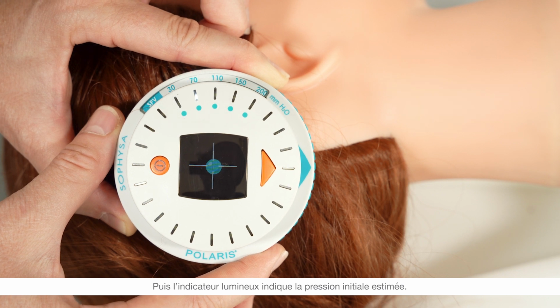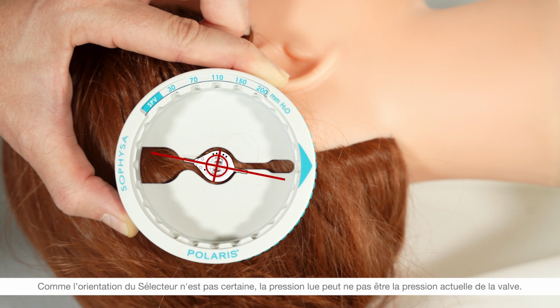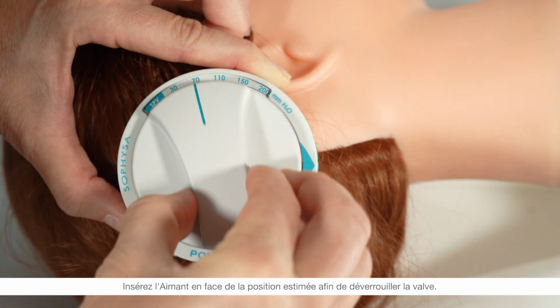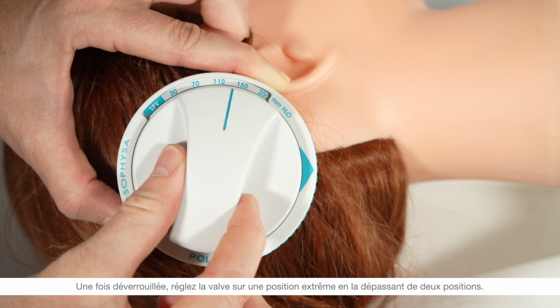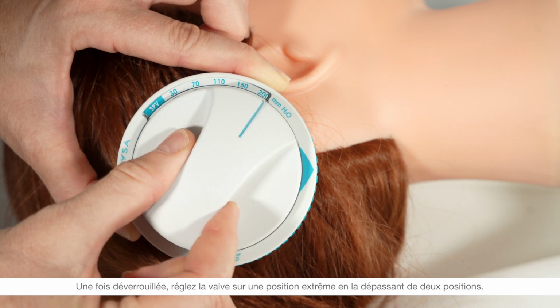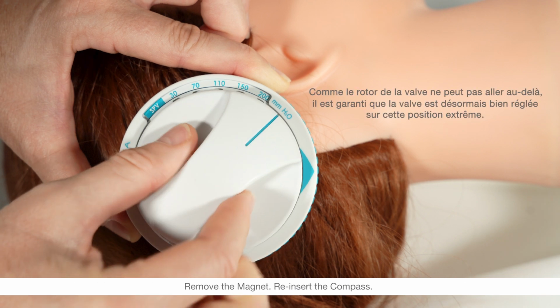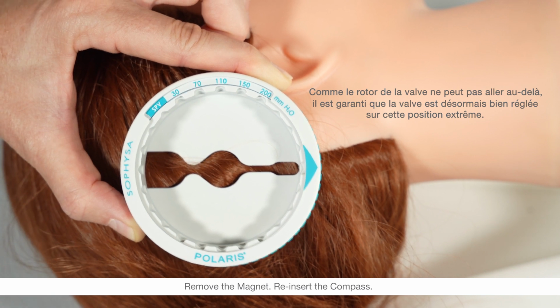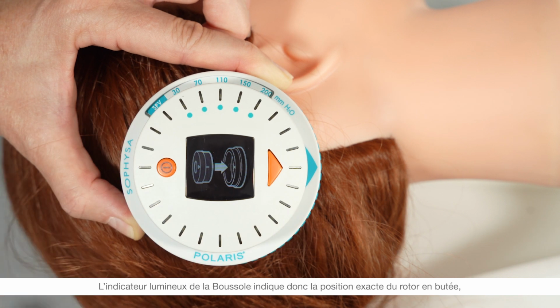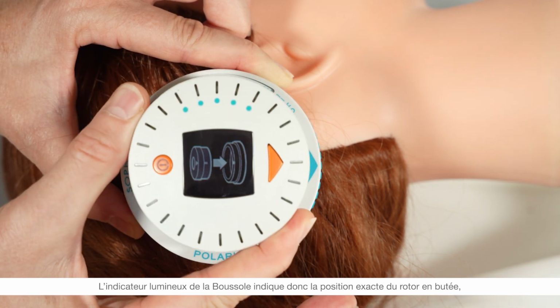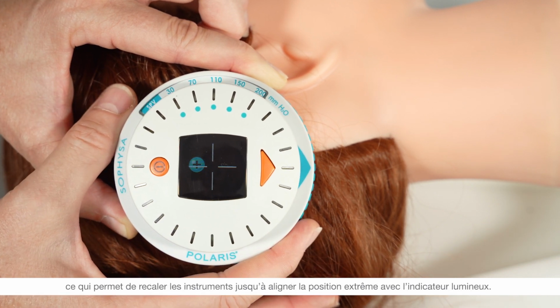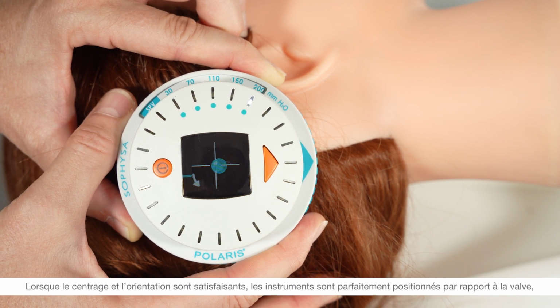Because this scenario involves an implanted valve whose exact flow orientation axis is uncertain, the apparent current pressure setting may not be the actual pressure setting. The stop method will eliminate this uncertainty. Insert the magnet into the locator in the axis of the apparent current pressure setting and rotate the magnet to either extreme pressure setting position, lowest or highest, and exceed that position by 2 clicks further. Remove the magnet. Reinsert the compass. The compass will confirm the extreme setting low or high. Using this extreme position as a known starting point, the adjustment can now be performed following the standard adjustment method.